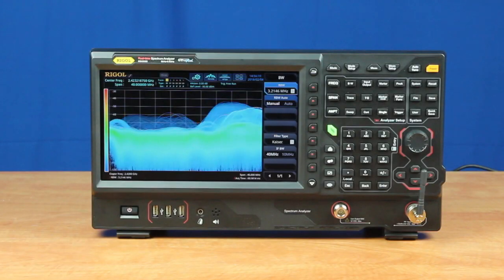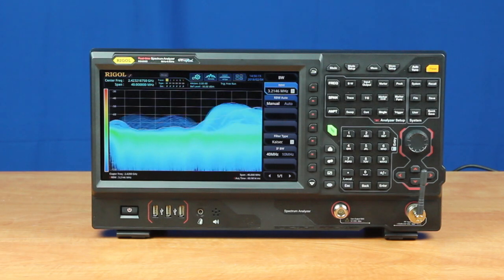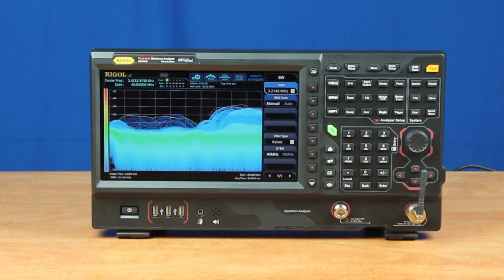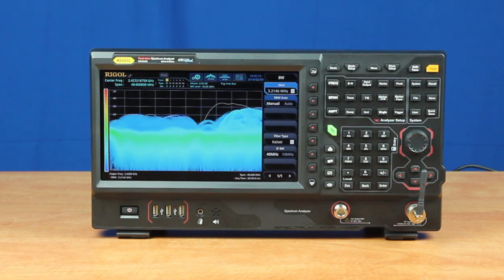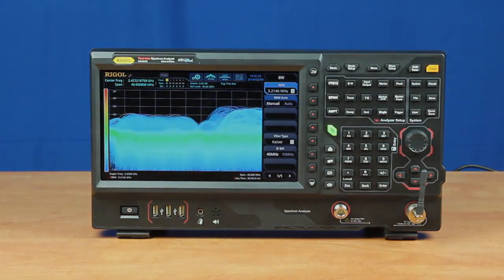So, use the RSA5000-BW40 option to extend the real-time bandwidth to 40 MHz and improve real-time measurement capabilities by making it possible to expand the resolution bandwidth and improve the 100% POI to 7.45 microseconds.